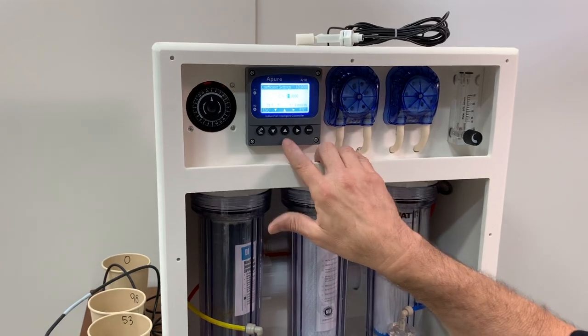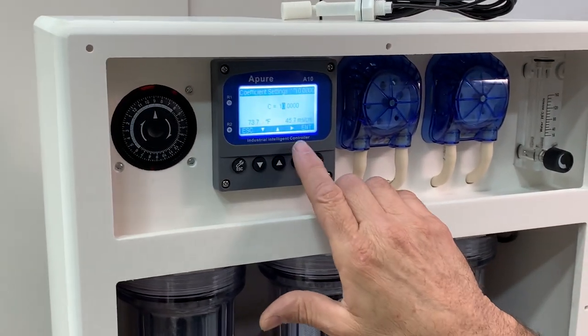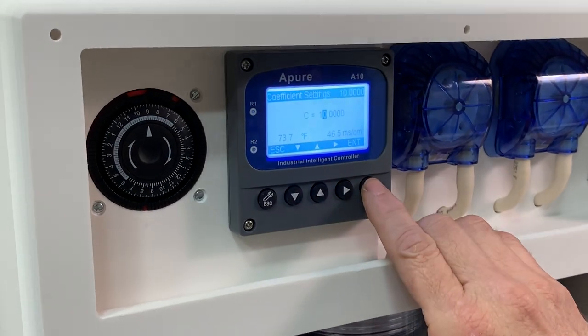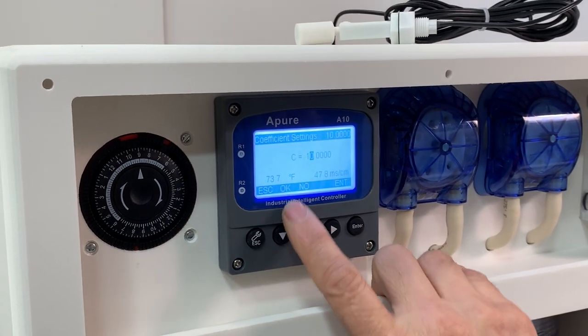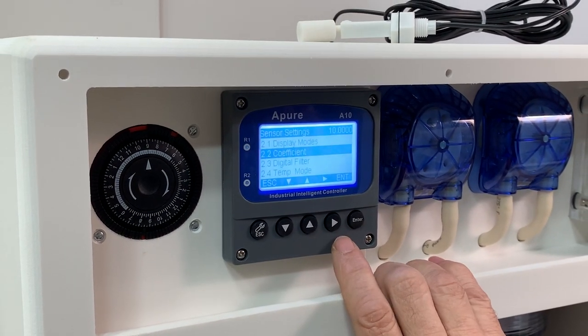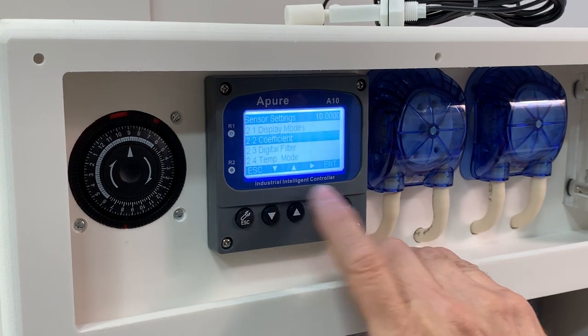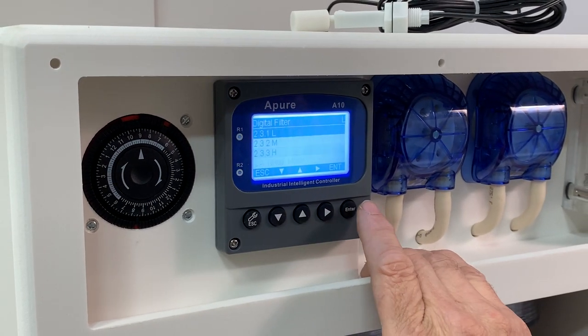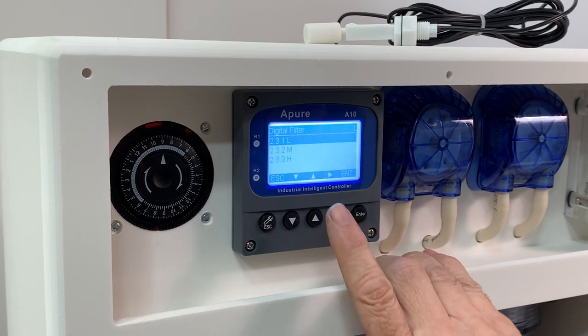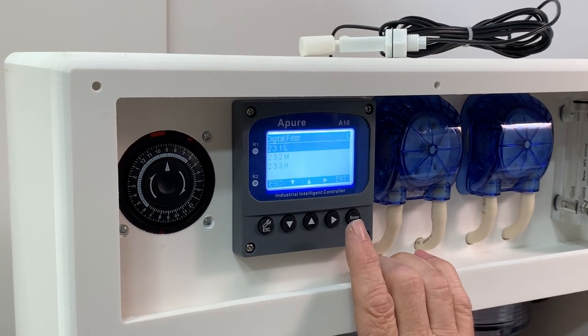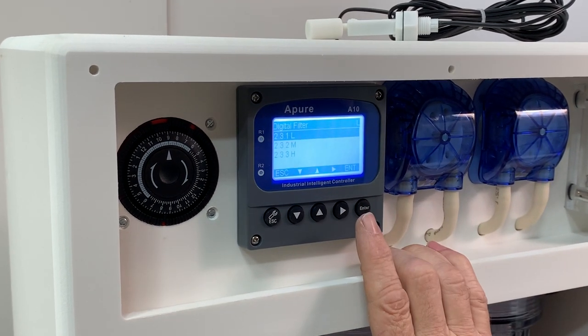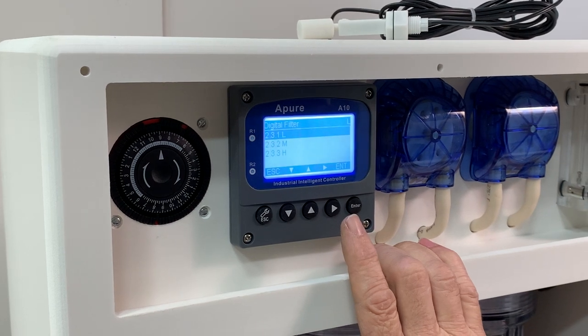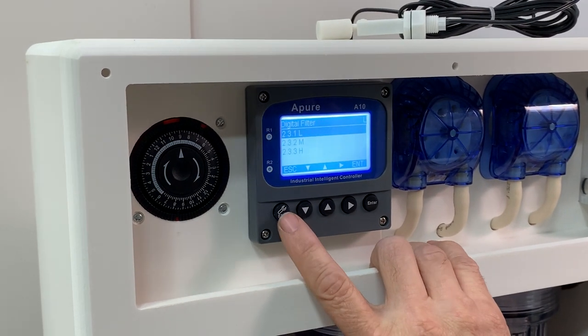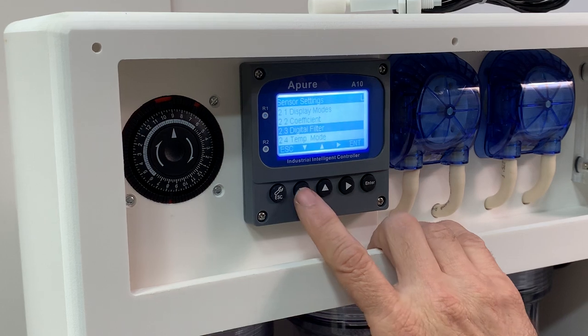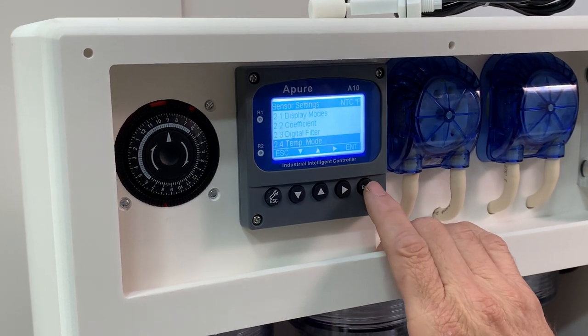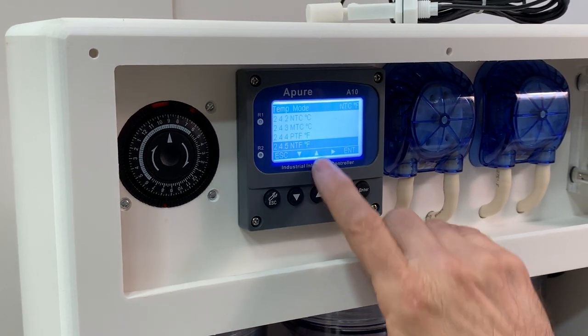So we're going to go back here to 10. Then I'm going to hit enter and it's going to ask me, are you sure? And I'm going to say okay. I like the digital filter to be set at low. There's low, medium, high. Basically, it just dampens the oscillation of the machine. It makes it a little more deadened so it doesn't flop around so quickly. And the temperature mode on this particular controller is set to NTC.